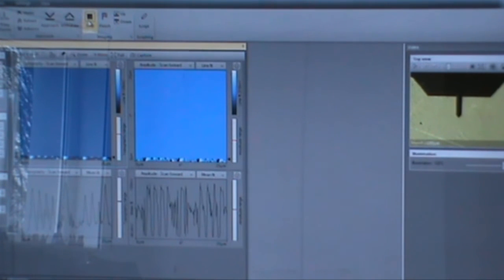After the scan is finished, it is automatically saved and can be edited by several tools included in the software. As shown, an image can be recorded within several minutes. Next, the cantilever or sample could be changed to gain additional information of the present sample or to investigate further samples. The use of advanced measurement methods is supplied by optional expansion packs.